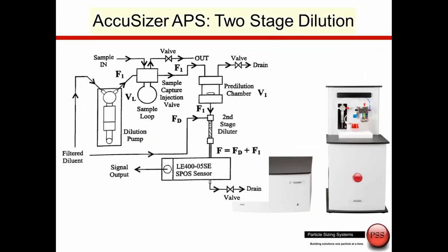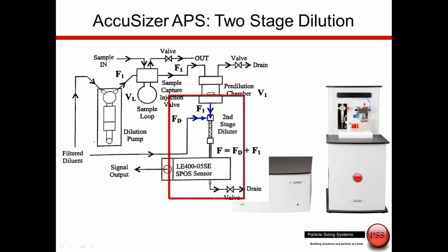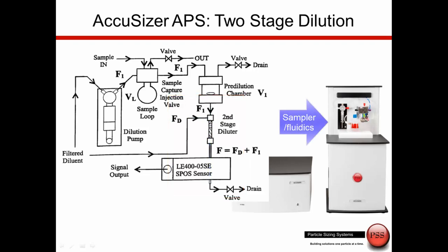For higher concentrations, the AccuSizer APS is a two-stage dilution system. The sample is pumped into a sample loop, then transferred to a pre-dilution chamber for the first stage of dilution. The second stage occurs as the sample is brought down to the sensor through an additional line of filtered diluent, with a controllable flow rate to adjust the final dilution factor. The sample can be pumped into the chamber or injected directly — one of three introduction methods — and then goes through this two-stage dilution for measurement.